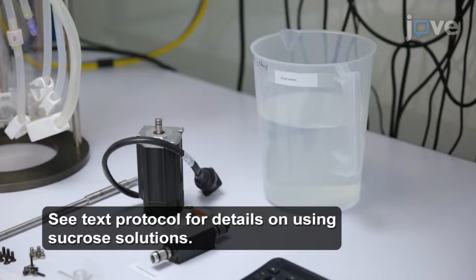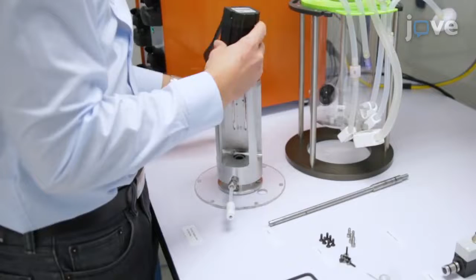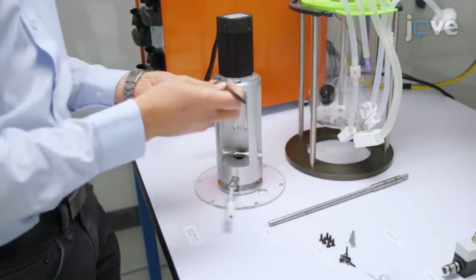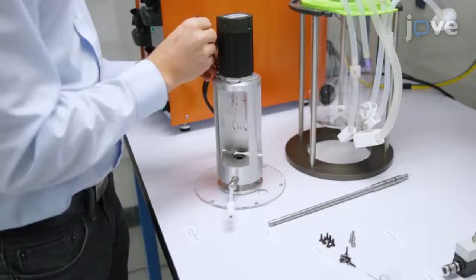The first step is to mount the agitator motor and the torque transducer. First, place the brushless servo agitator motor onto the top of the holder, and secure the motor in place with screws. Then orient the torque transducer properly and put it in position, and fix it on the holder.